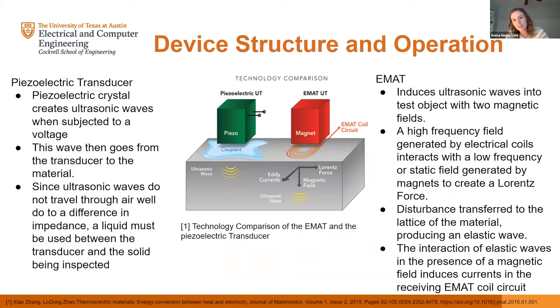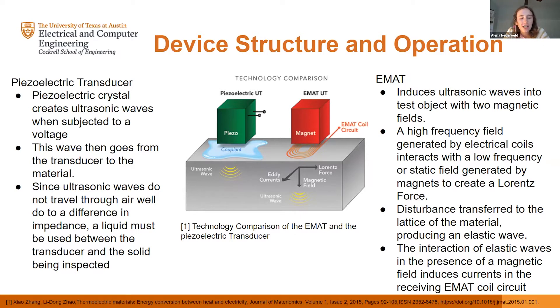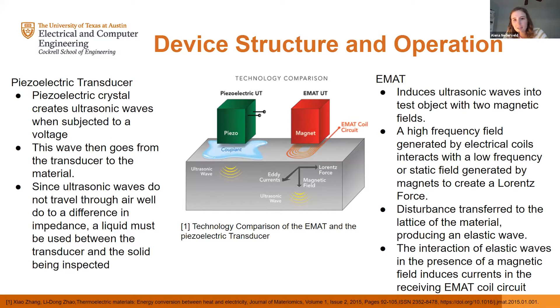Comparing EMATs to the traditional piezoelectric transducer: a piezoelectric crystal creates ultrasonic waves when subjected to a voltage, and the wave goes from the transducer to the material. The catch with piezoelectric transducers is that ultrasonic waves do not travel through air well due to the large difference in impedance, and therefore a liquid couplant must be used between the transducer and the solid being inspected.